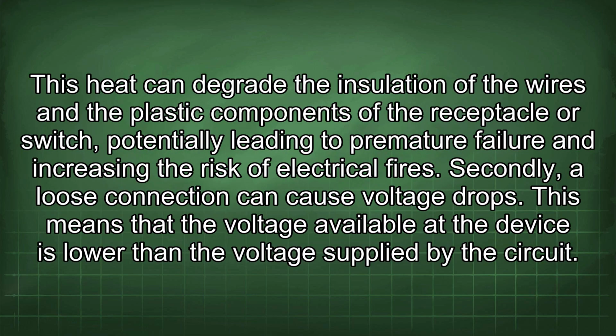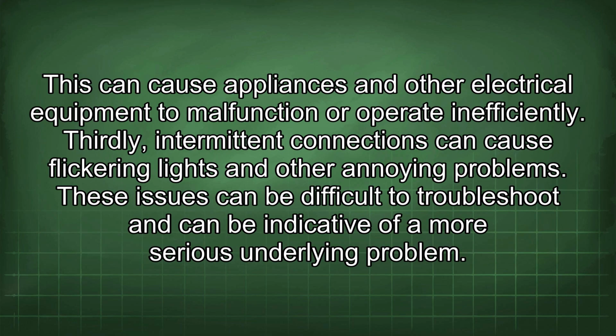This heat can degrade the insulation of the wires and the plastic components of the receptacle or switch, potentially leading to premature failure and increasing the risk of electrical fires. Secondly, a loose connection can cause voltage drops. This means that the voltage available at the device is lower than the voltage supplied by the circuit. This can cause appliances and other electrical equipment to malfunction or operate inefficiently. Thirdly, intermittent connections can cause flickering lights and other annoying problems. These issues can be difficult to troubleshoot and can be indicative of a more serious underlying problem.